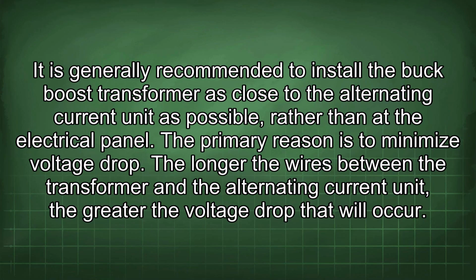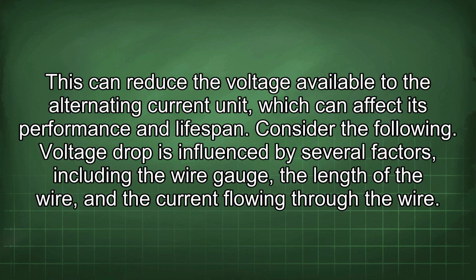It is generally recommended to install the buck-boost transformer as close to the alternating current unit as possible rather than at the electrical panel. The primary reason is to minimize voltage drop. The longer the wires between the transformer and the alternating current unit, the greater the voltage drop that will occur. This can reduce the voltage available to the alternating current unit, which can affect its performance and lifespan.